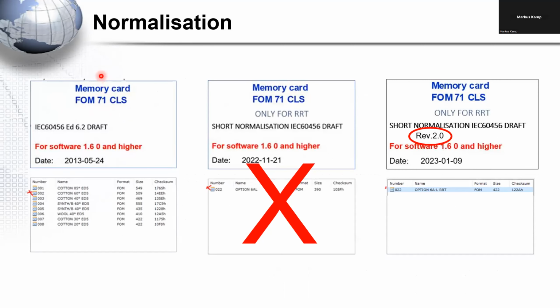Here you see the memory cards delivered by SwissAttest. On the left, there's a memory card for the standard reference programs. In the middle, that was the second card where a wrong program was on, so throw it away or destroy it, and afterwards you should have got, or you get it now, the third card, and it's called short normalization revision 2. This is the correct card, and here you see the program name is, as mentioned before, option 6A-L and RRT at the end. That's important. That's the correct one for the short normalization program.